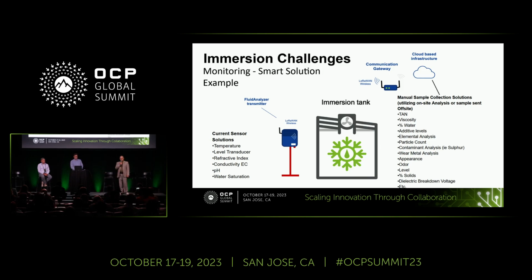Another contribution is from Brian Kincaid, who shared with us their long years of experience on how to evaluate in real time and in lab tests the properties of the dielectric fluid, bring that all together in one place in the cloud, and predict and maintain the fluid. This is also in our workstream, and we are happy to share that information with other members.